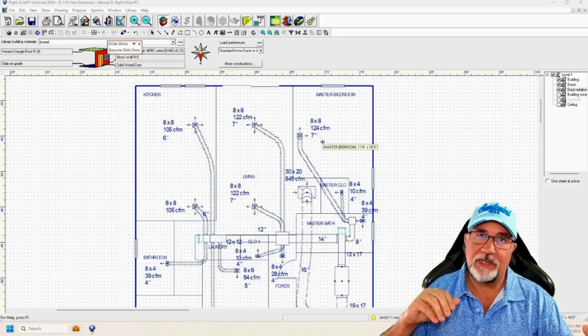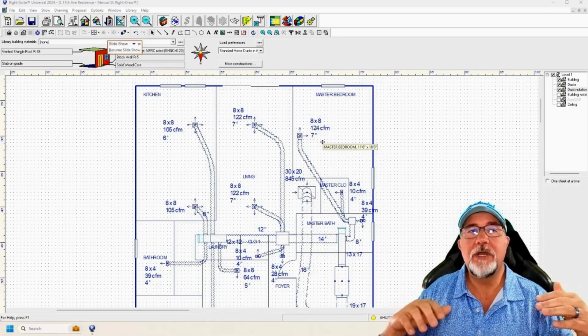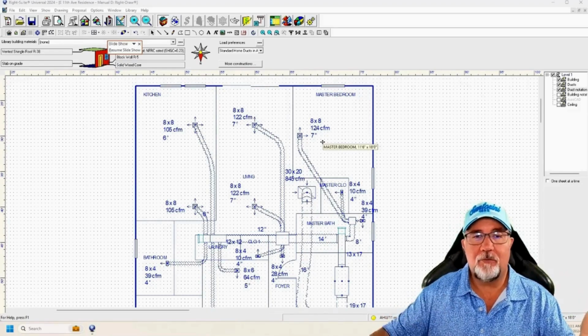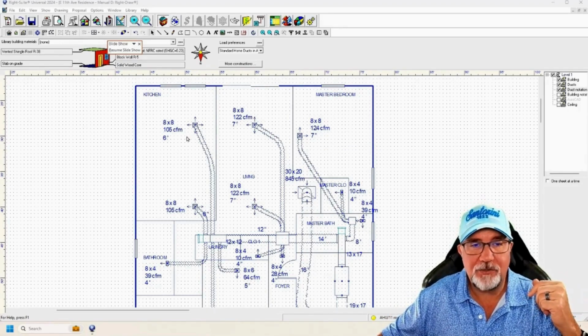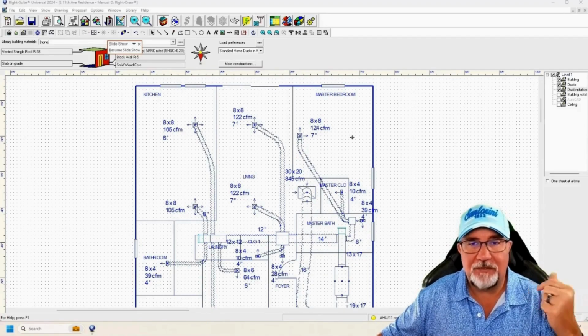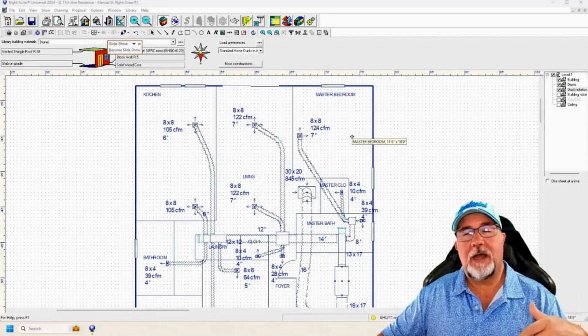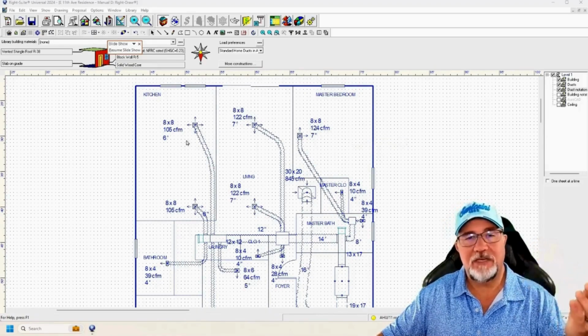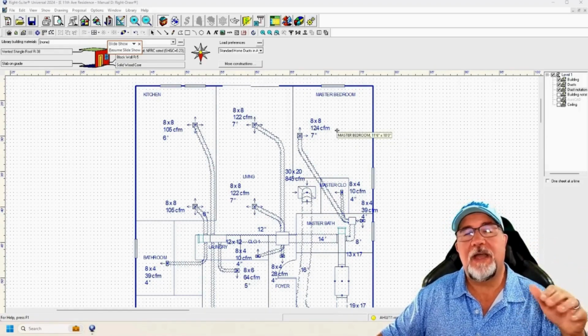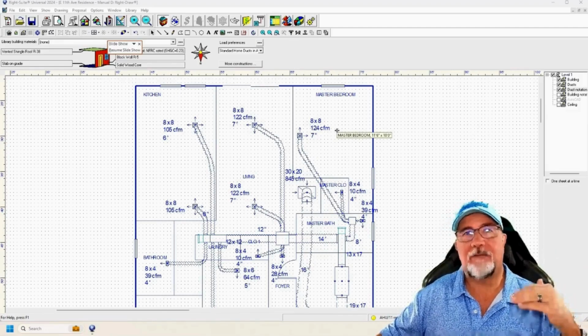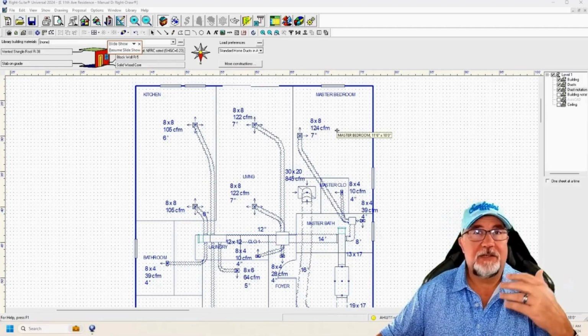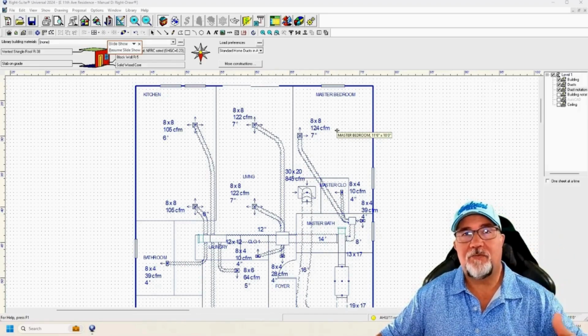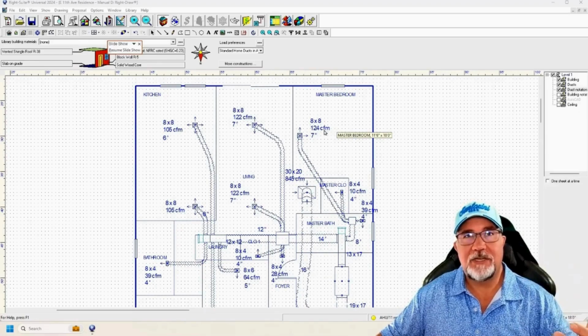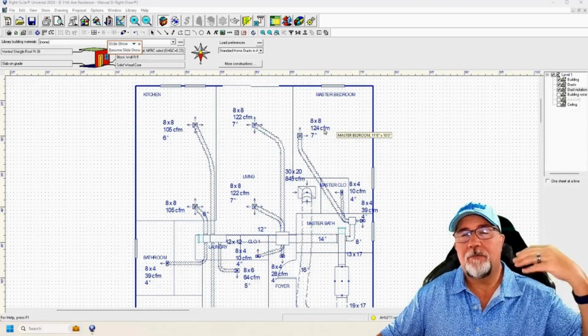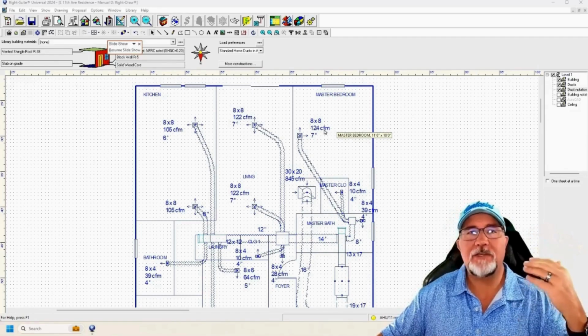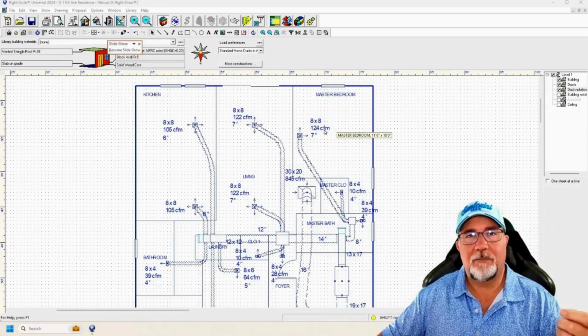What direction does the room face? How many windows? What other potential issues are in that room? For instance, if I measure the kitchen and it comes out the same size as the master bedroom, and I put the same size duct in both, that kitchen is going to be hot as can be. Why? Because, as we talked about last week, there are different heat loads in the kitchen—the stove, refrigerator, small appliances, and other things that have to be factored in.